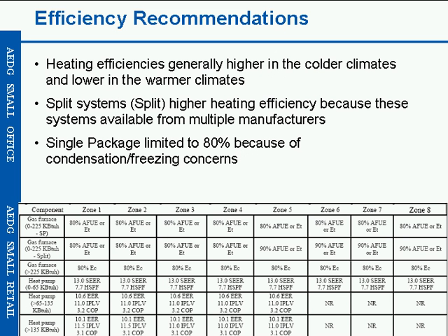So now if we look at the heating efficiencies contained in the small office and small retail, again, the heating efficiencies are generally higher in the colder climates and lower in the warmer climates. You'll see the gas furnace efficiencies for a split system as well as a single package, or the SP abbreviation there. The recommendations are consistent across the smaller systems, the 0 to 225,000 BTU per hour systems, at 80%.